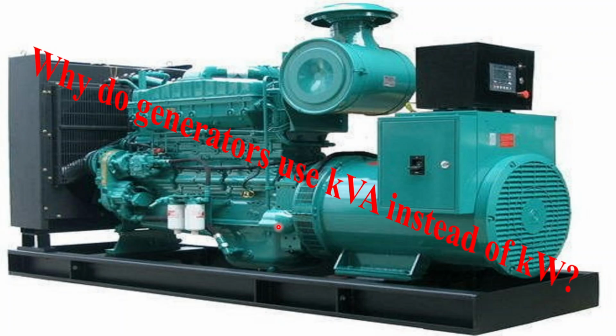Electrical system design is the fourth reason. Electrical components like transformers, conductors, and generators are typically rated in kVA because they are designed to handle total apparent power, which affects their thermal limits and voltage regulation capabilities. Using kVA accounts for the fact that both real and reactive power contribute to the total current that components must handle, ensuring system reliability and efficiency.